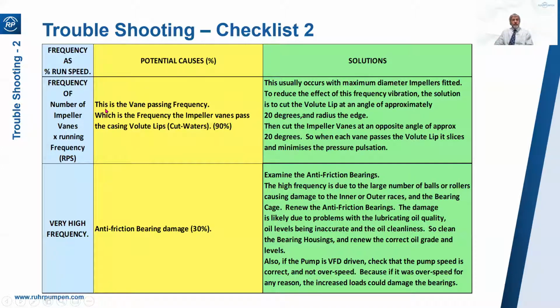Vane passing frequency. The frequency that the impeller vanes pass the casing volute lips or cutwaters. And 90% of the time it's going to be that. However, that is something that you're going to see as a design issue on a new installation. It's not something that you're going to see during ordinary running. It's not a wear problem. So it's something that you might possibly see from the outset.